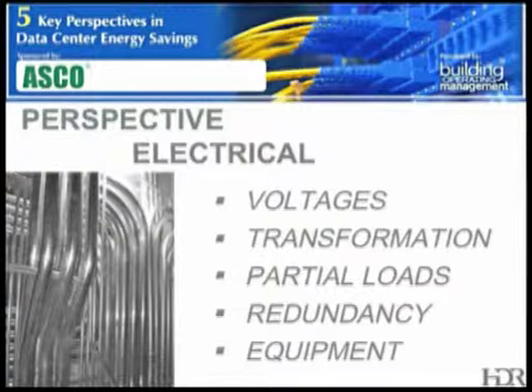There's lots of options we have to improve power system efficiency. Typically, we're either removing or moving components in the power path or changing a way that the data center operates, whether we're raising the distribution voltage or virtualizing servers or something to that effect, or even using more efficient components. Some of the key fundamentals that we work with when we're talking about changing the voltage or transformation, and Bob Haley talked about this earlier, is there needs to be pre-design work. Designers need to coordinate the rack voltage with IT, the server density with the IT group, and make sure that those are situated in the best positions for the electrical and mechanical distribution.